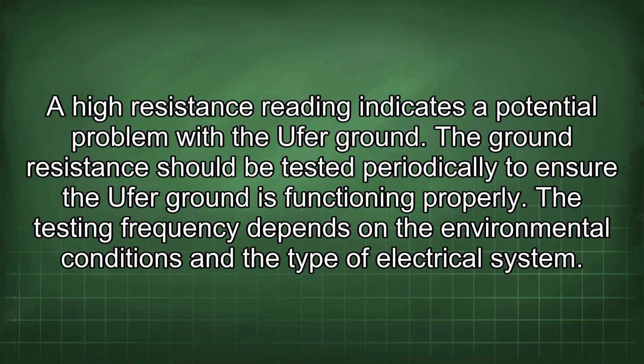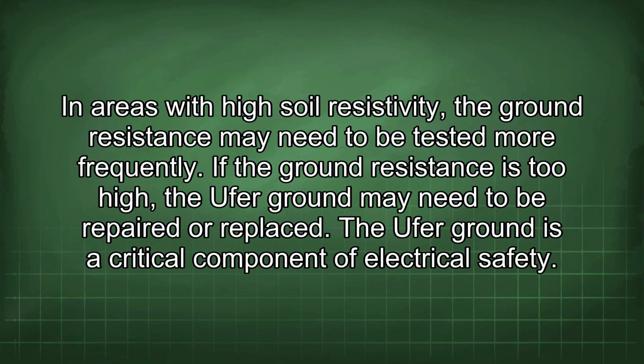The ground resistance should be tested periodically to ensure the Ufer ground is functioning properly. The testing frequency depends on the environmental conditions and the type of electrical system. In areas with high soil resistivity, the ground resistance may need to be tested more frequently. If the ground resistance is too high, the Ufer ground may need to be repaired or replaced.